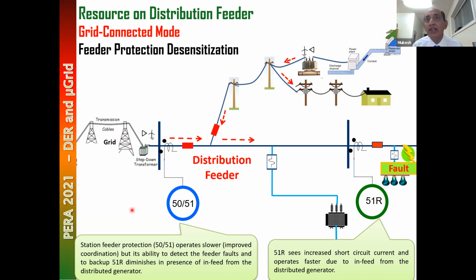The point I'm making is that there's a protection desensitization here. You have to look at it and accommodate it: you have to do protection changes, you have to do system changes, and you need to install more protection reinforcement if that's the case. Typically, the good news is this desensitization is not there for phase faults. It is mostly there for ground faults. Why for ground faults? Because ground faults have a resistance in them. Phase faults do not have resistance.